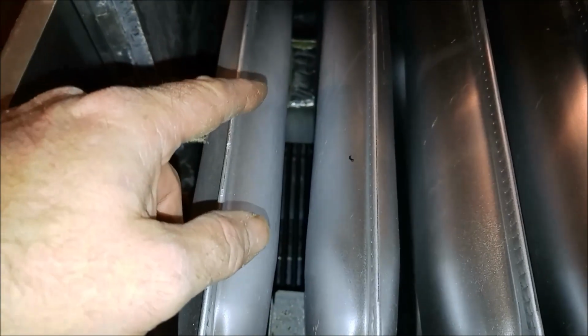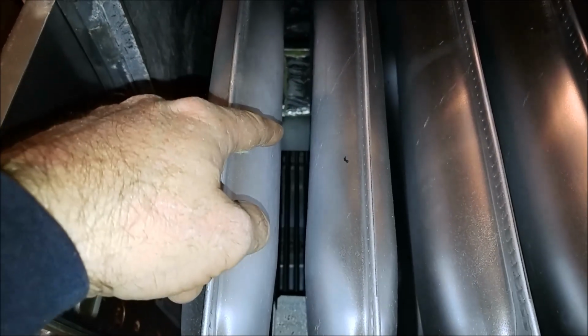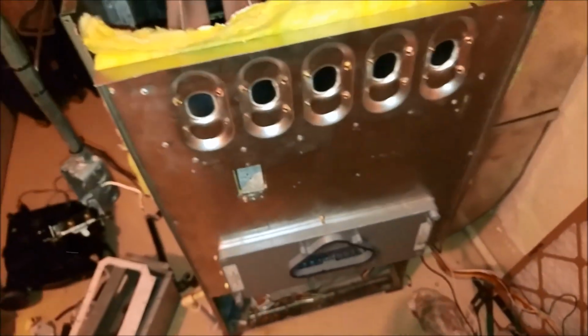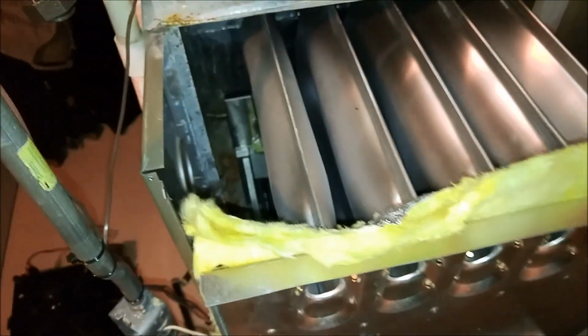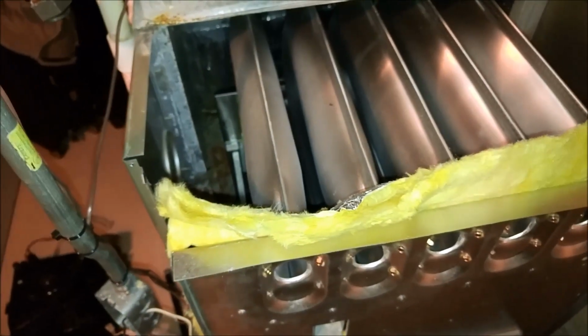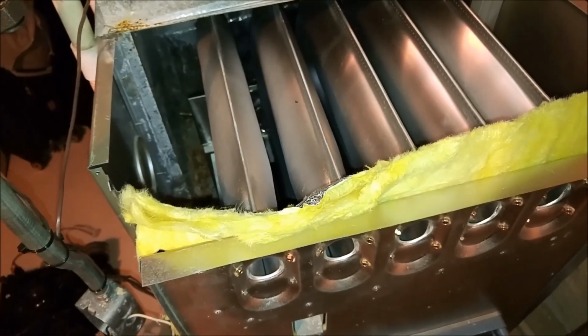When that blower air hits that baffle plate back there, it directs it up towards the limit right here. Limit sits right in here like so, so it directs air up there. If you ever run across one of these replaced and someone forgot to put that baffle in, yeah, you're tearing the whole heat exchanger out again.